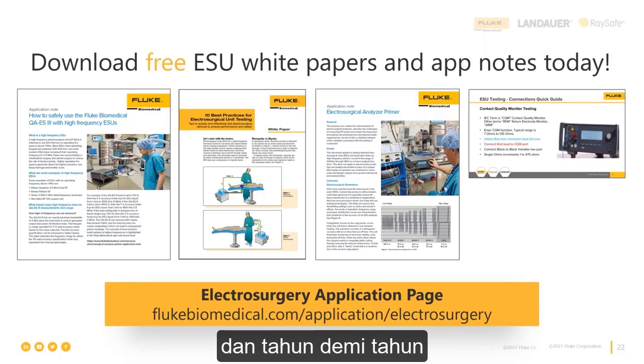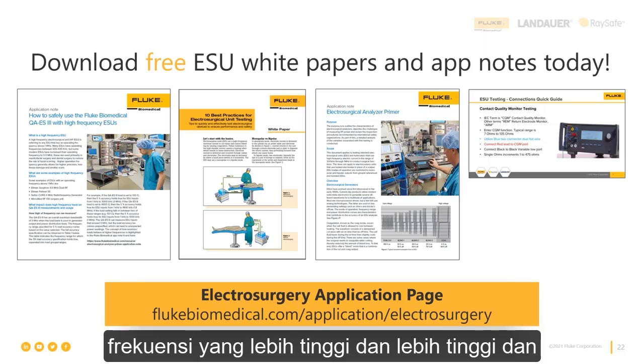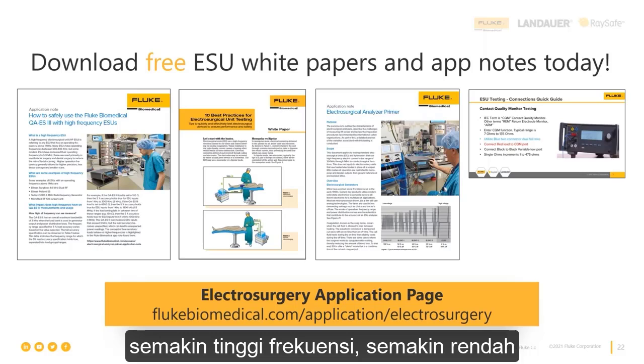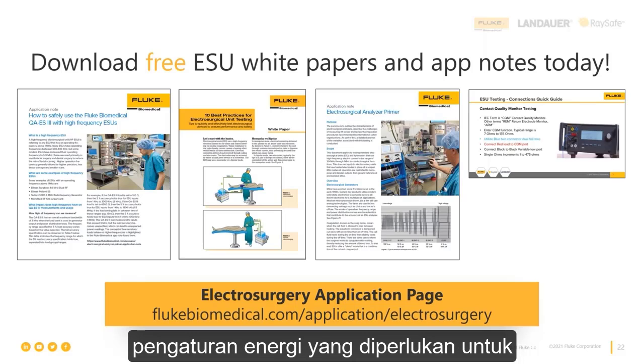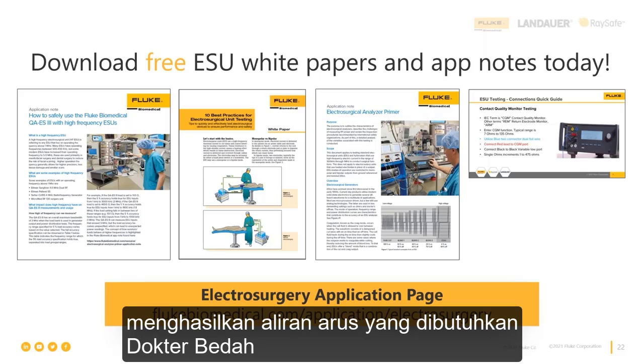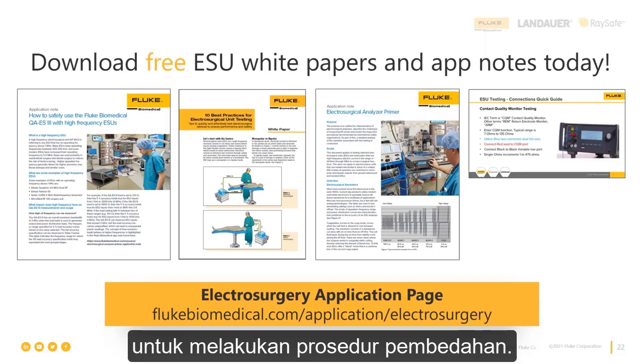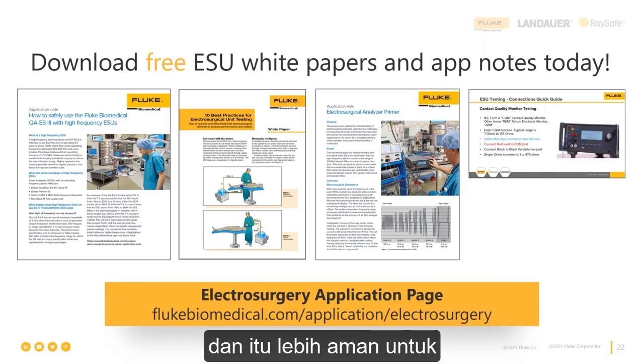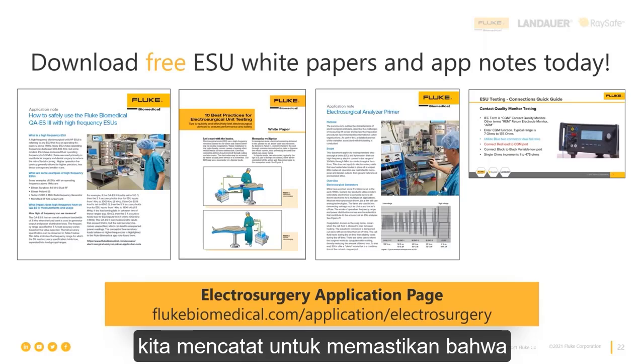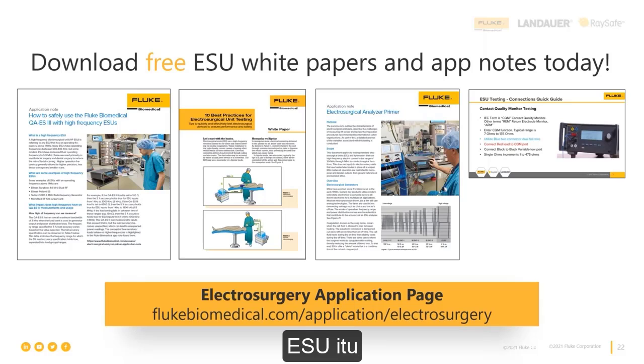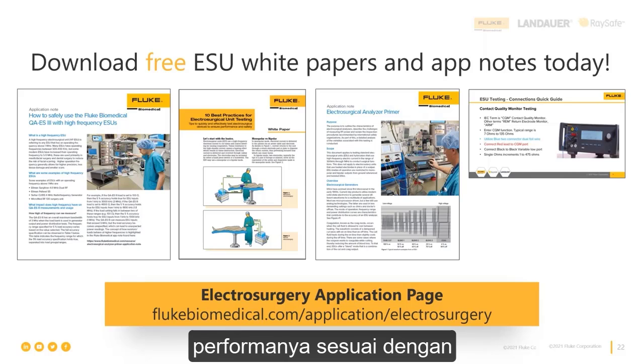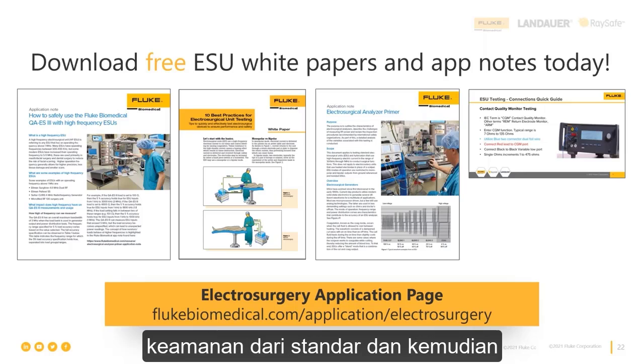And year by year, ESU manufacturers are pushing the frequency higher and higher. The reason for that is the higher the frequency, the lower the energy setting needs to be in order to produce the current flow that the surgeon needs to do the surgical procedure. And it's safer, by the way, for the patient, as long as we're keeping track of making sure that that ESU is performing according to its manufacturer spec and the minimum performance and safety from the standards.